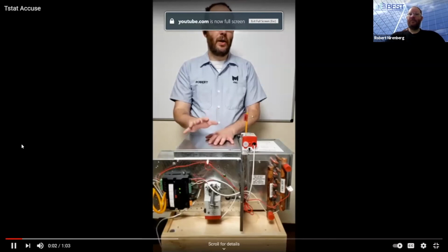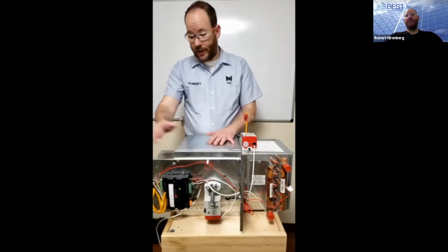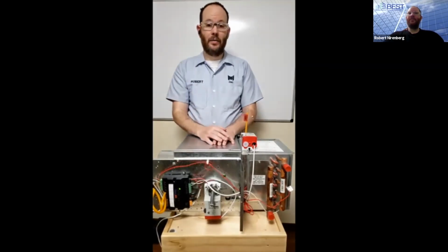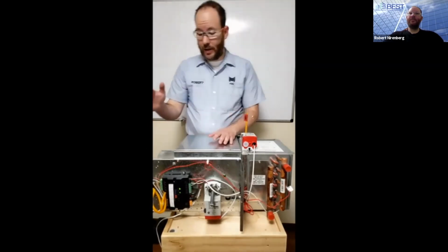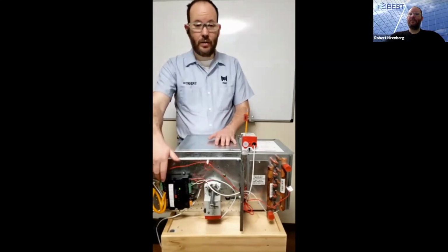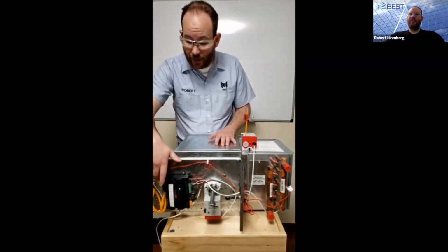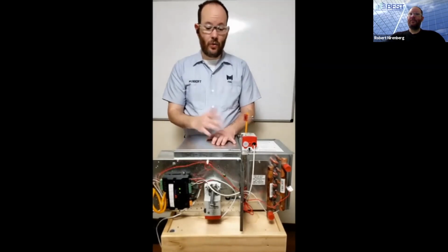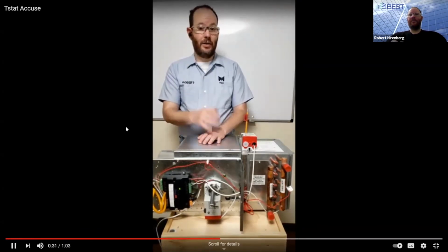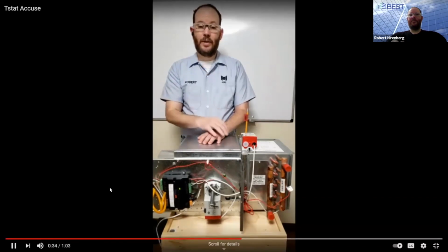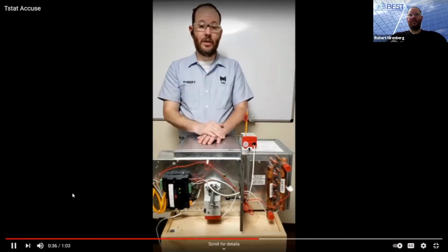So you think you've sorted out the problem with this particular VAV box, and you believe it has to do with the wiring of the thermostat. There you are correct. If you look closely at the wiring in the thermostat and the wiring on the controller, you'll notice that the set point and the temperature sensor wires have been swapped. So we have been monitoring the room set point as the temperature. The set point doesn't change until someone fiddles with the knob, so the system always thinks it's a constant temperature.